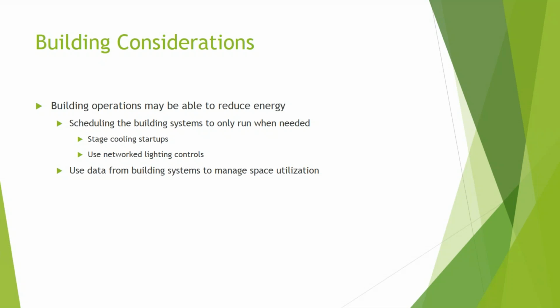For example, during the day, occupancy sensors might be set to a 10-minute timeout, but outside of normal work hours, the network could change those occupancy sensors to operate with a walkthrough mode, where they might not even turn on lights if they don't detect people there for a few moments.